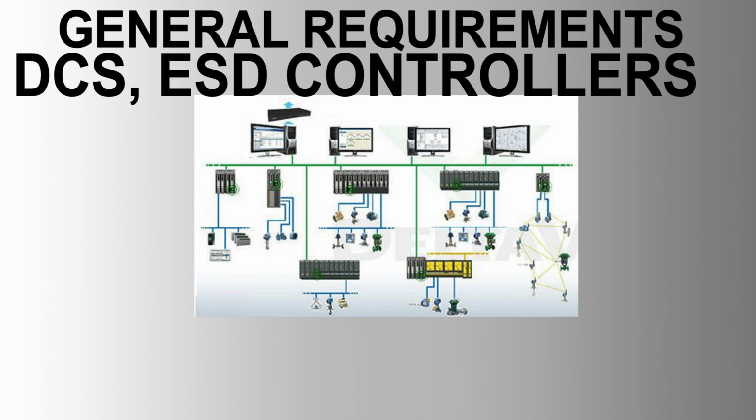6. Availability. Redundancy. The design must ensure no single point of failure. The design should be 2 by 100% at all levels. All clients must be designed so that any local failure results in the loss of only one client. Each component of DCS must have dual redundant power supply modules. Automatic bumpless switchover for redundant components and communication links. Capability for global access by tag number to each process and calculated variable from any node.